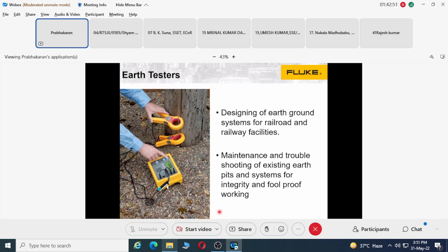Maintenance and troubleshooting of existing earth pits and systems is needed for integrity and foolproof working. You may have an earthing system that's 100 years old or 10 years old, but if you really want to find out how these earthing wires or systems are working, you need better test tools to do that.